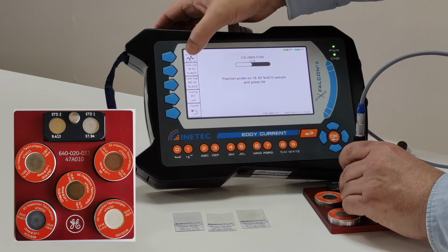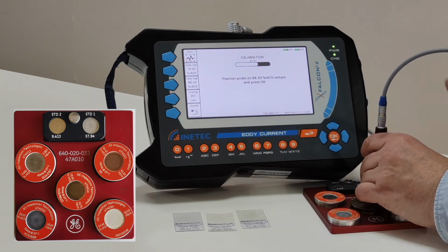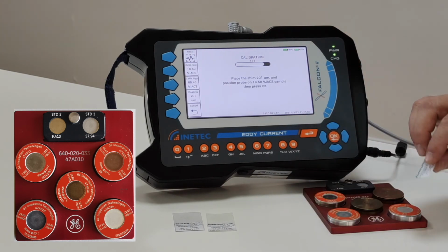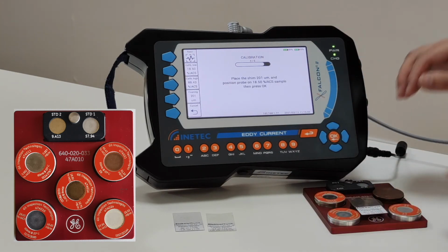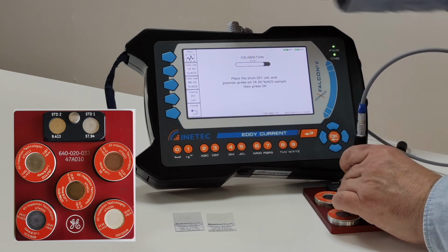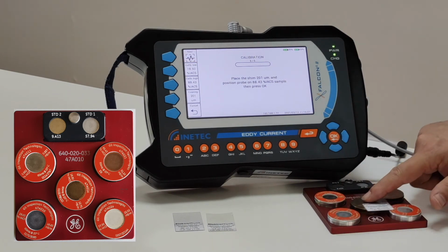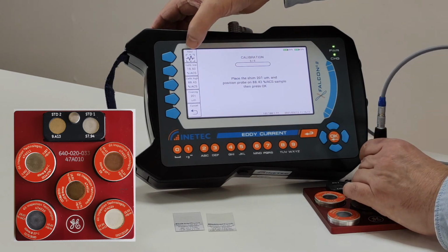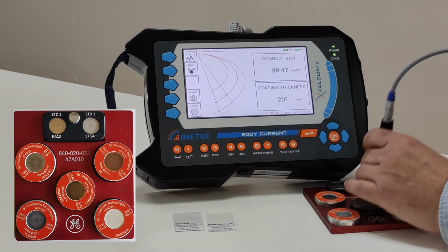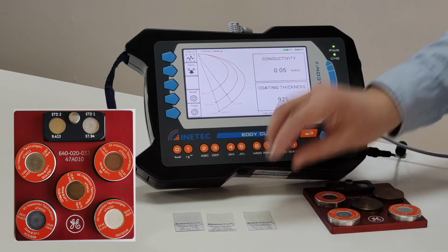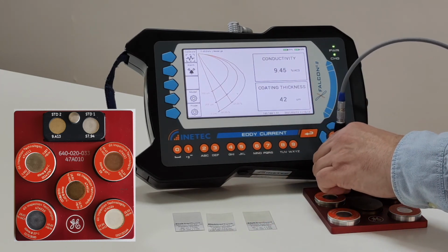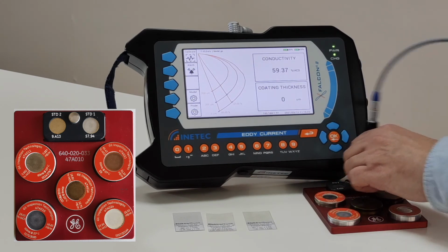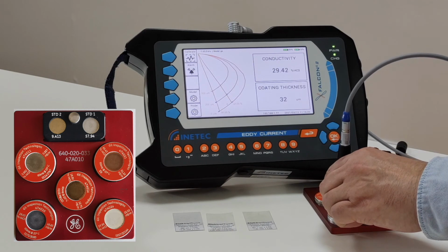Air, 2 conductivity calibration blocks, and 1 known non-conductive material shim in combination with conductivity calibration blocks are selected. After calibration, we can check the accuracy of measurements on all conductivity samples and non-conductive material shims.